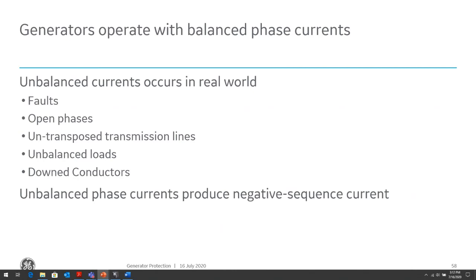So when we talk about unbalance, what kind of conditions will cause unbalance in the generator, or what kind of conditions will the generator see unbalance in? Obviously fault currents, but there are other scenarios where we'll see unbalance. Open phases, open conductors in the system, if it's an overhead line, untransposed transmission lines where we have coupling across the transmission line, the various phases of the transmission will couple against each other, which will cause unbalance within the system. Unbalanced loads, obviously, and those unbalanced conditions produce negative sequence currents.